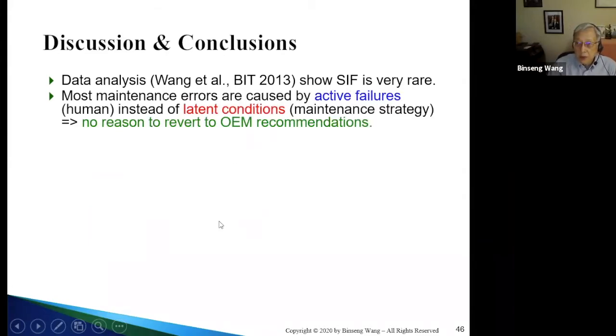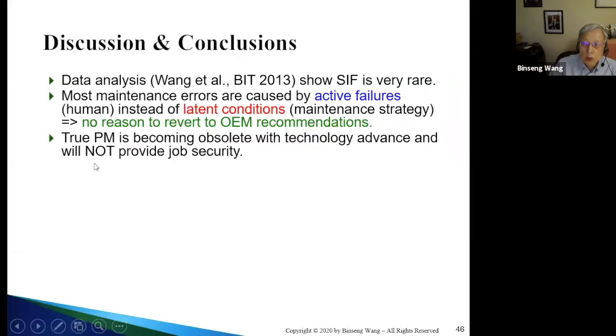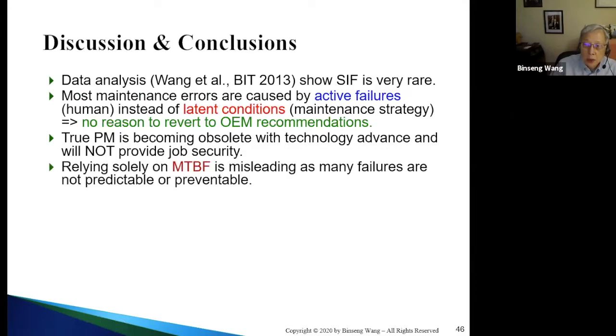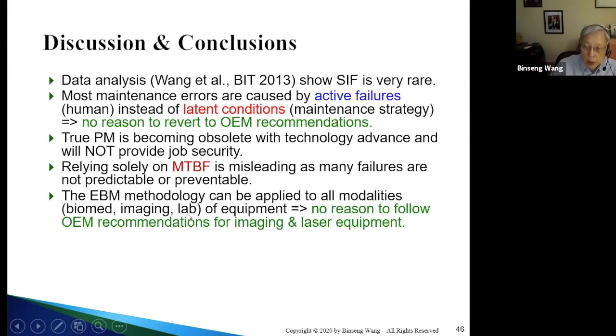The service-induced failures are very rare. Most maintenance errors are actually active failures by human beings instead of latent failures. In other words, accidents, people using the wrong things, accessories that are not good, or batteries not being recharged. And the reality is that true preventive maintenance is becoming obsolete because technology has evolved very fast. Most of the things now are solid state electronics. So relying on mean time between failure, as I mentioned before, is dangerous because a lot of failures are not predictable or preventable.